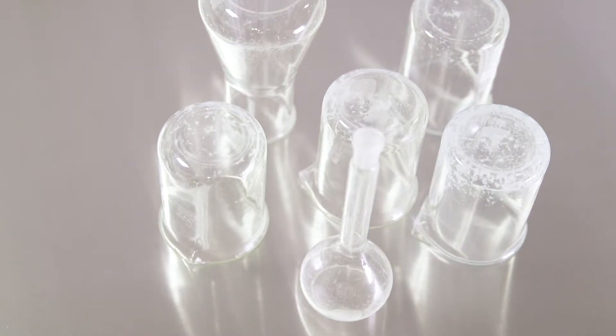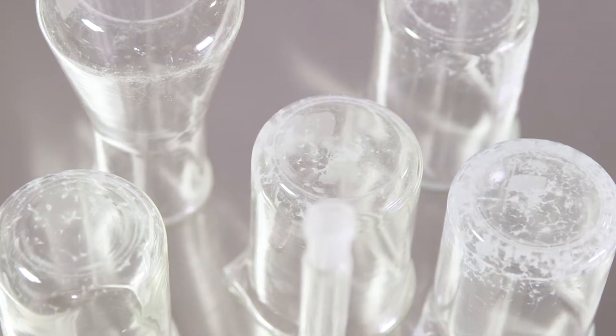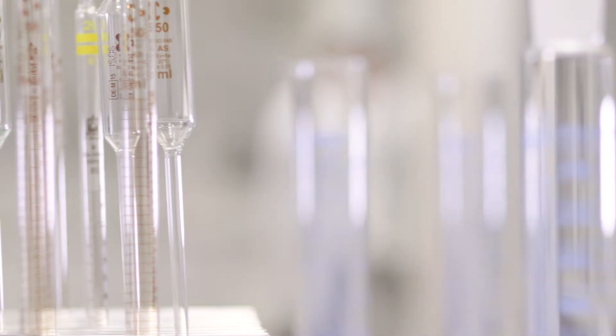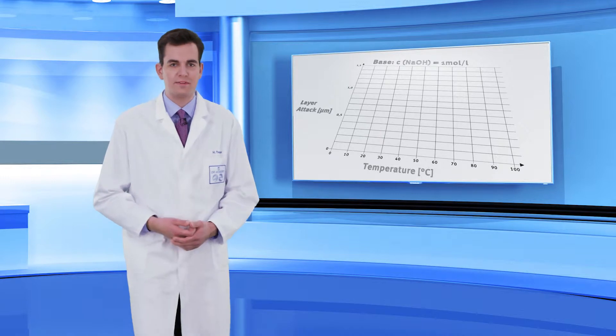Glass corrosion is a structural change in the glass surface that leads to a loss of accuracy in volumetric instruments, such as pipettes, laboratory glassware, or measuring flasks. Glass corrosion can be caused, for example, by selecting the incorrect cleaning procedure.